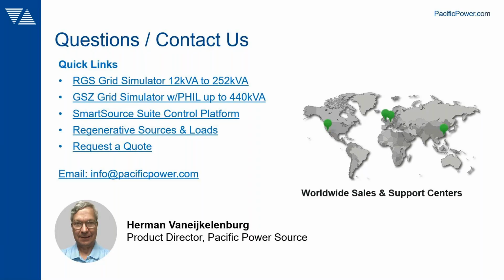Which real-time simulators can be connected to your grid simulators? For example, Opal RT, Typhoon, etc. As long as they're analog I/O, it doesn't really matter which hardware you use, but the interfaces, connectors, layouts, and pinouts are not the same between different manufacturers. So each would require the right physical adapter to route the right signals into the HIL interface on the power source of the grid simulator. They can be interfaced electrically and mechanically, but it requires different adapters for different brands of simulators. There is some effort to standardize, but at the moment every manufacturer of HIL systems has their own pinouts and connectors.